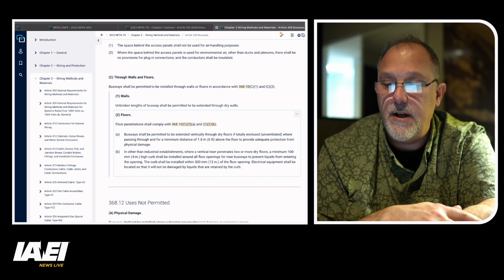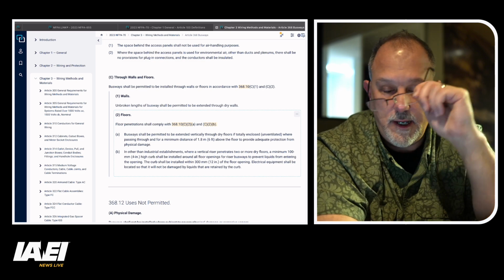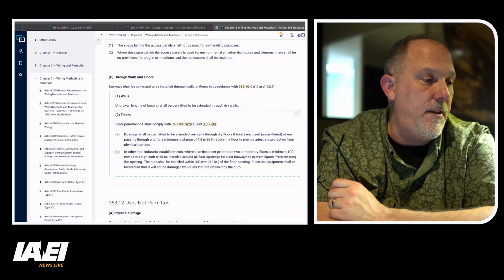Floor penetrations, etc. So what we're basically trying to tell you is you want to make sure that when you're using busway, the connection points, the splicing, extending lengths of busway in a series motion, you don't want any of those terminations in an area where you don't have access. So if you're going through a wall, don't splice it right there in between the two rooms. So make sure that you're extending in an unbroken length of the busway through that wall. All right? So that's your through walls and floors.